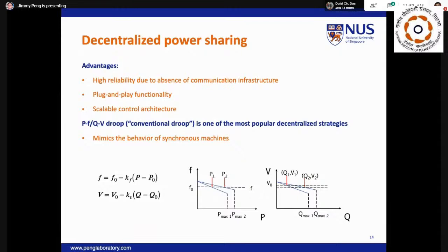The concept of Droop is actually borrowed from the classic power engineering, where the output power is varied based on the variation in frequency, or the output reactive power is varied based on the voltage deviations. The rate of response is defined as a gain, which is KF for the PF Droop and KV for the QV Droop.